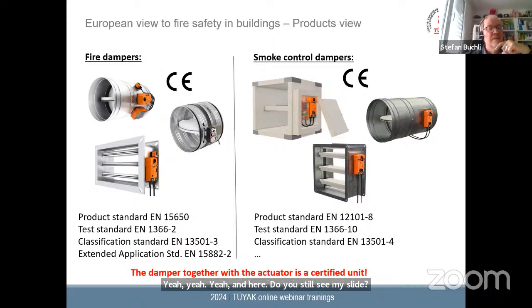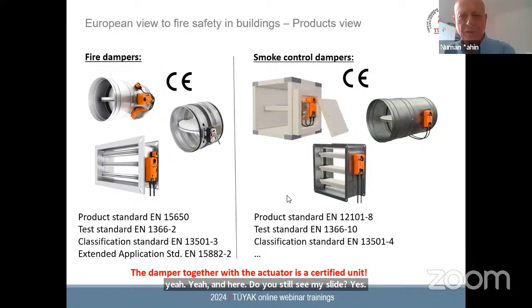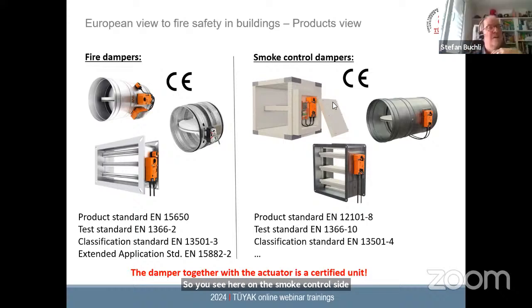Yes. So you see here on the smoke control side different constructions. Yes. One construction looks actually like a fire damper, and there you see that the actuator is not protected. This is the so-called automatic activation solution. That means this smoke control damper is activated very early in a fire by the smoke control system, and just operates once. So the temperatures are still low, it can be operated, and then the actuator just has to hold the damper in its position, either open or closed, during the whole duration of the fire.